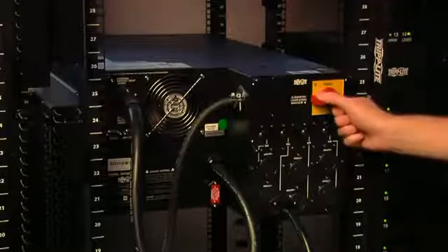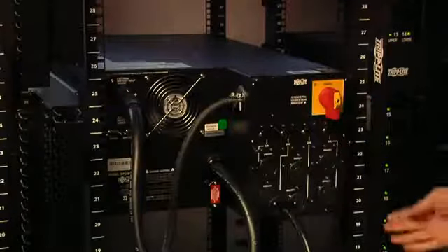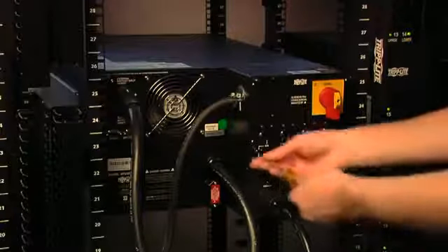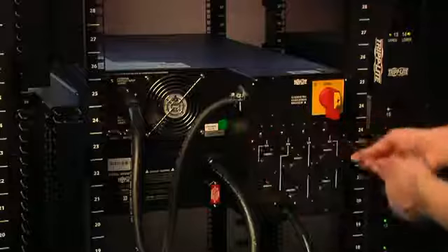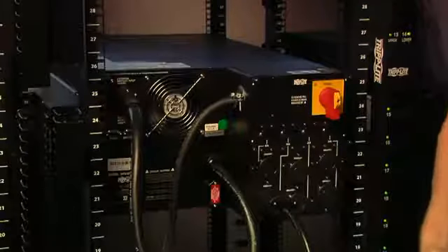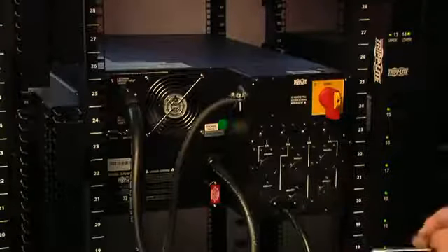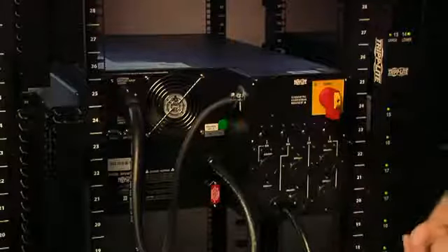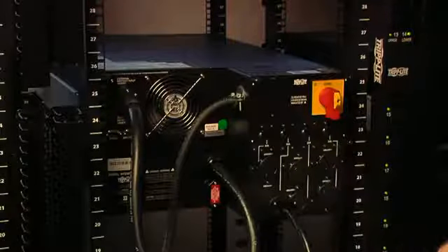Now with the new power module energized, I can return the system to a normal state. You can see all of the load lights remain powered, and of course I would secure the balance of the screws for a final installation. We've hot swapped an 8 or 10 kVA power module without ever downing the load.